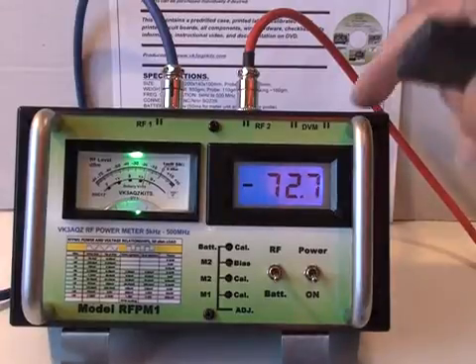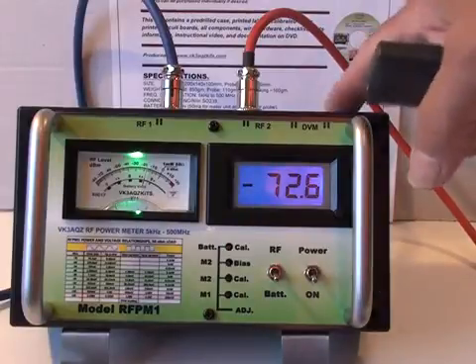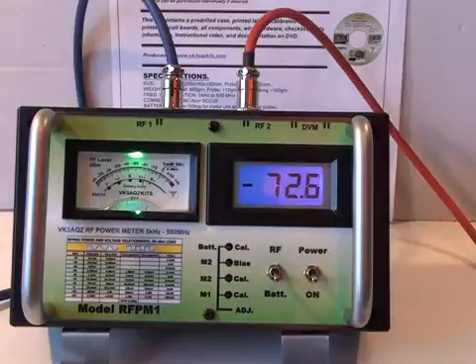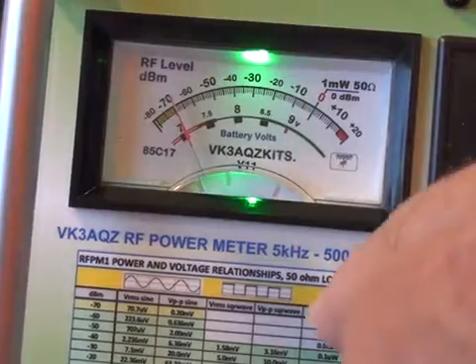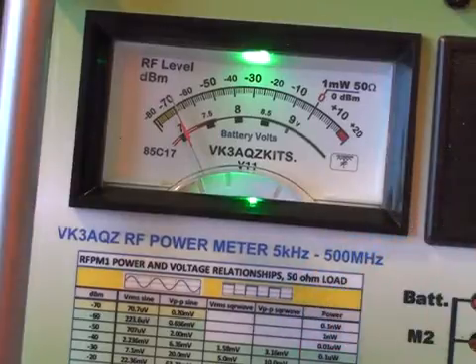In addition, any modulation on the RF signal that the detector probe is picking up can also be observed on these two terminals. The frequency response of the meter within a dB or so is from 5 kHz to 500 MHz.